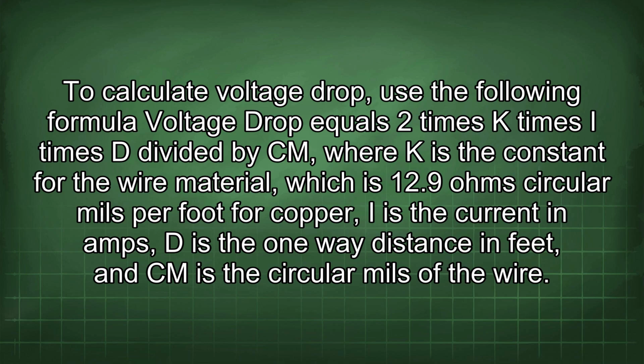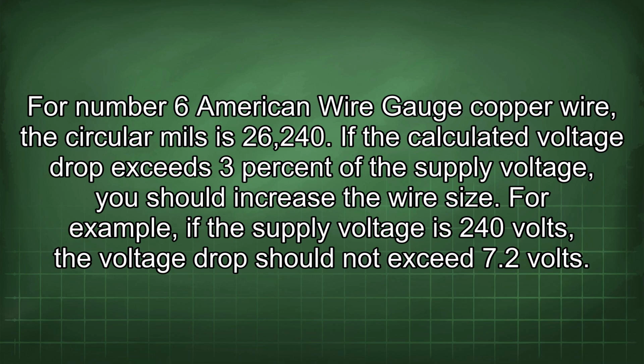the wire. For number 6 American wire gauge copper wire, the circular mils is 26,240. If the calculated voltage drop exceeds 3% of the supply voltage, you should increase the wire size. For example, if the supply voltage is 240 volts, the voltage drop should not exceed 7.2 volts.